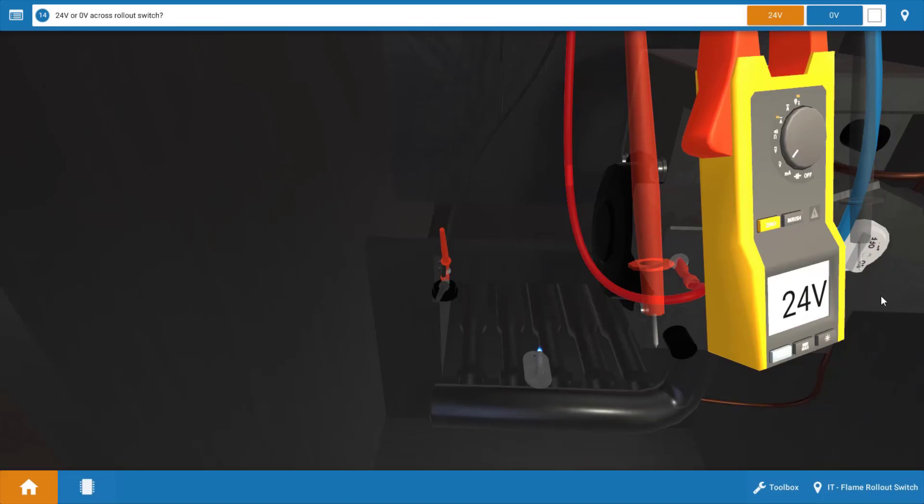Now listen, before replacing it, make sure you look at the burners and they may need to be cleaned. They may have some evidence of rust or corrosion that's resulting in a delayed ignition, or it's possible you have some type of exhaust fan or possibly a clothes dryer nearby that's pulling the flames out of the front of the boiler, causing the rollout switch to trip.